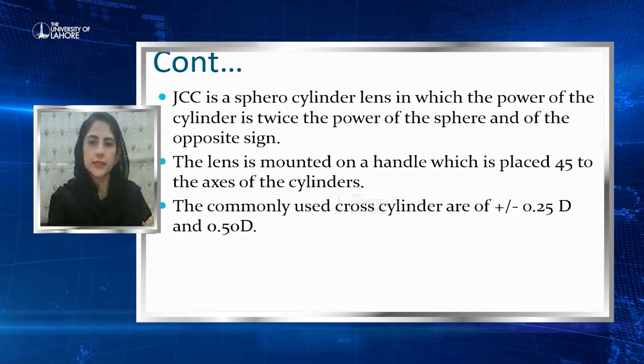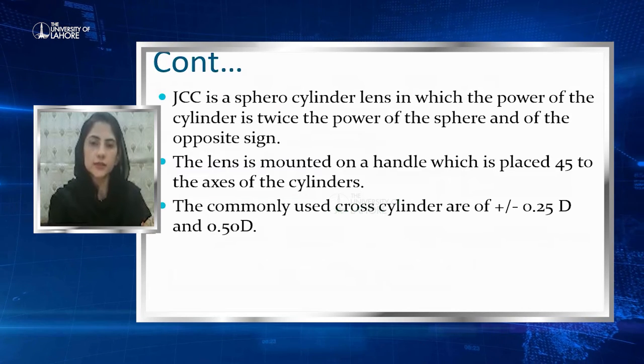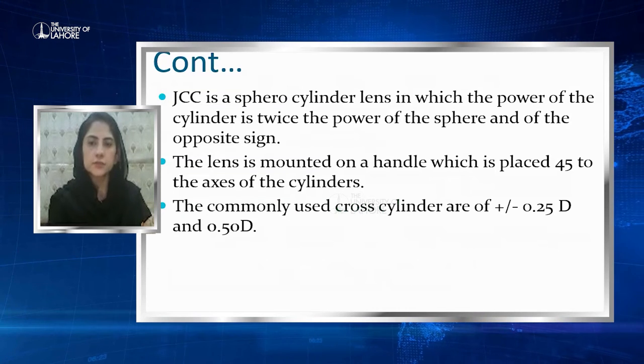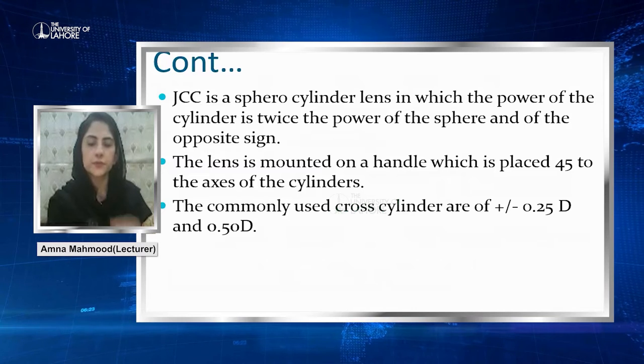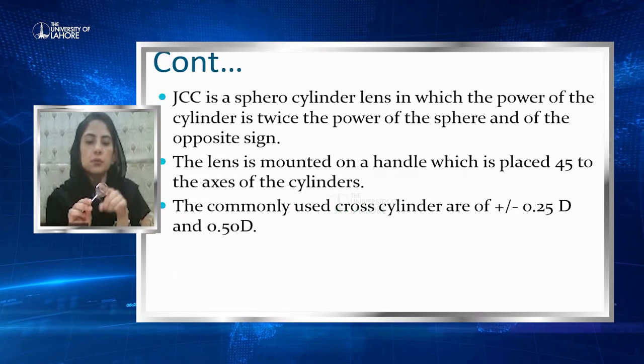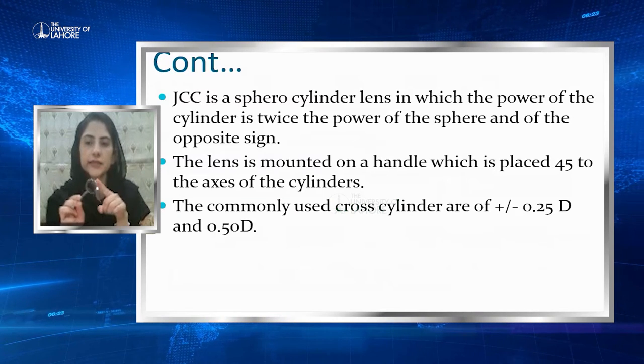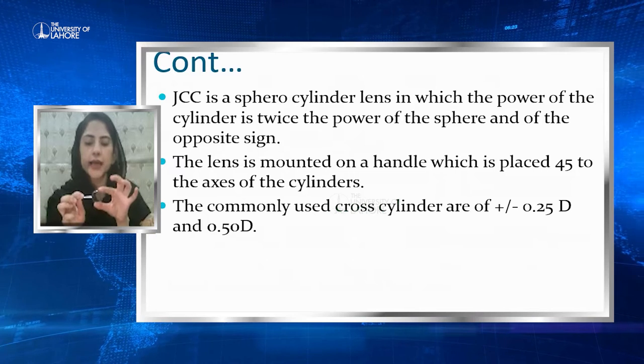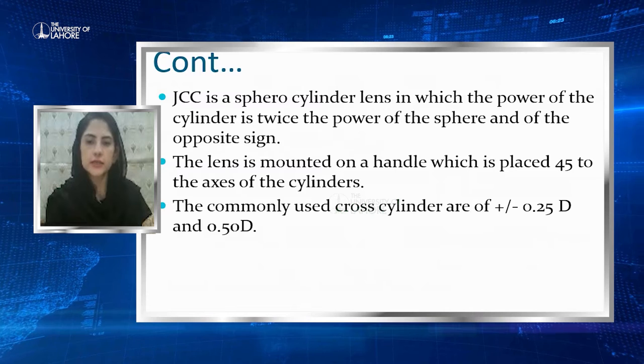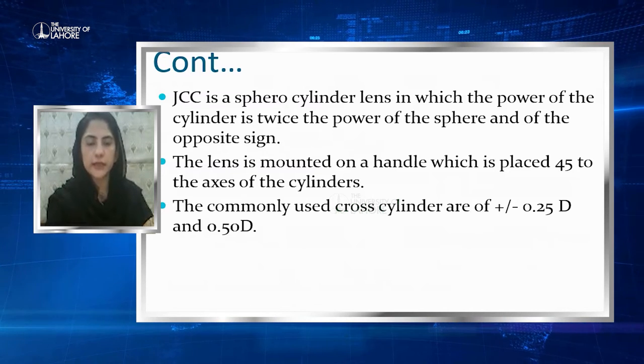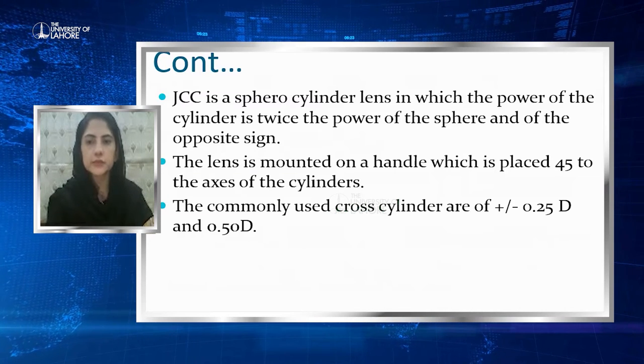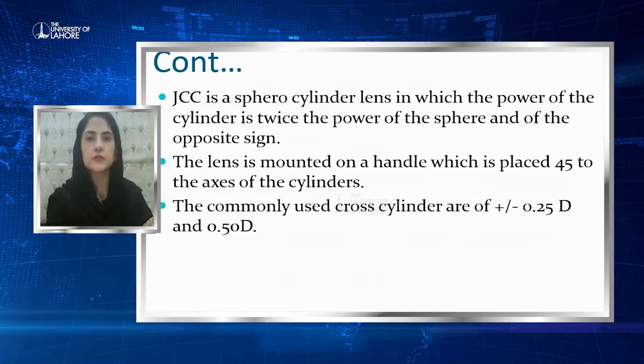The Cross Cylinder is a special cylindrical lens in which the power of the cylinder is twice the power of the sphere and of the opposite sign. The lens is mounted on a handle placed at 45 degrees to the axis. So, minus is at 90 degrees, plus is at 180 degrees, and the handle is at 45 degrees. The commonly used cross cylinders are plus/minus 0.25 diopters and plus/minus 0.5 diopters.